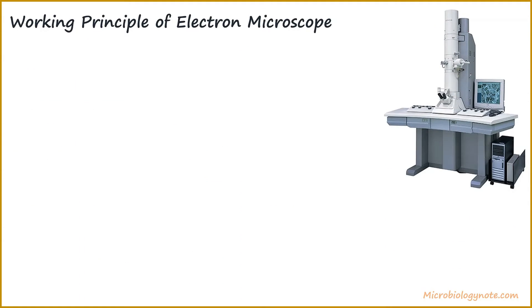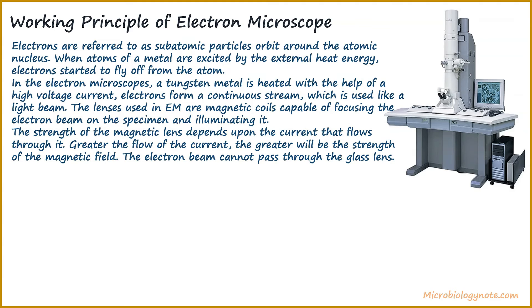Now we will talk about how electron microscopes work. Electrons are referred to as subatomic particles that orbit around the atomic nucleus. When atoms of a metal are excited by external heat energy, electrons start to fly off from the atom. In electron microscopes, a tungsten metal is heated with the help of a high-voltage current, and electrons form a continuous stream which is used like a light beam. Magnetic coils are capable of focusing the electron beam on the specimen and illuminating it. The strength of the magnetic lens depends upon the current that flows through it — the greater the flow of current, the greater will be the strength of the magnetic field. The electron beam cannot pass through a glass lens.